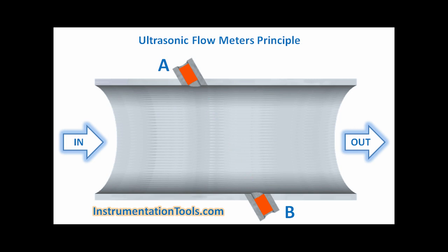As the flow speeds up, the time it takes for the chirp to travel with the flow will proportionately decrease, while the chirp traveling against the flow will proportionately increase in time to be detected.